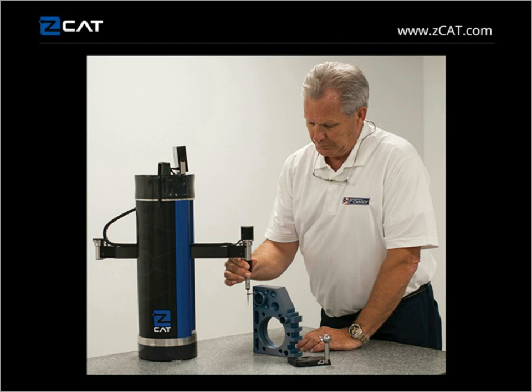Typical parts that we would use in a zCAT can be from very small to upwards to 20, 24 inches long. Because we do have a measuring range of around 27 inches, but because the gauge does sit in the center and the parts could be around it, we are somewhat limited, like any CMM on the part. You'll also see a standard on this picture. That's a 1-inch precision sphere that we use to do a calibration of the probe and the stylus.